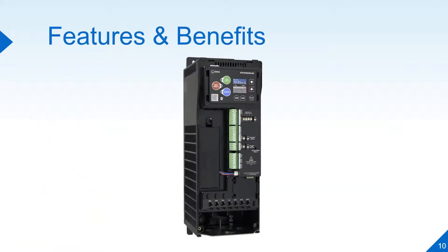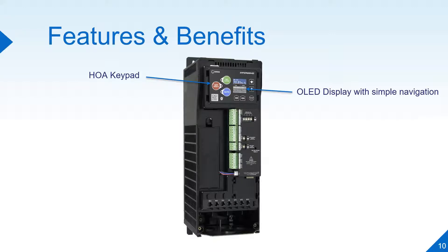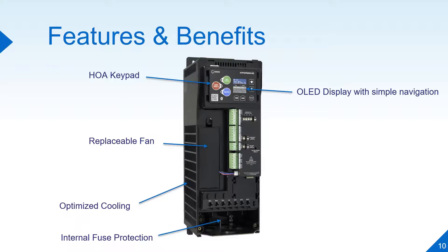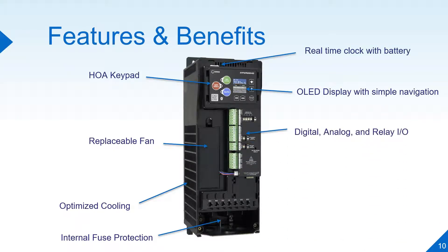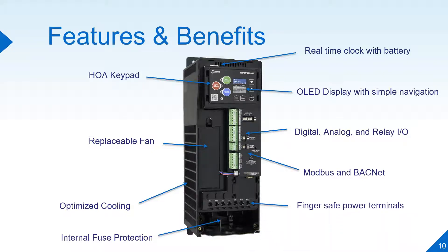Key features on the Q-Link VFD are the hand-off automatic keypad, the organic light-emitting diode display with simple navigation, the internal fuse protection, the easily replaceable fan, optimized cooling, real-time clock with battery, digital, analog, and relay inputs and outputs, native Modbus and BACnet communications, and finger-safe power terminals underneath the unit. Also, there is not currently a BTL listing for this product.